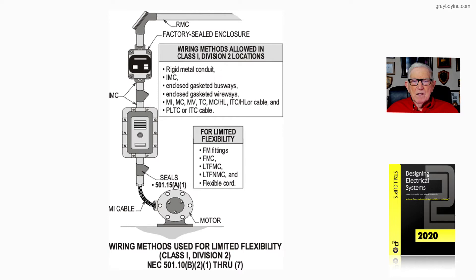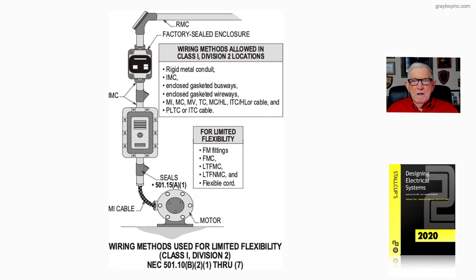Then down at the very bottom, we have a seal and we have MI cable, or we may have a flexible wiring method that is listed for limited flexibility. It's the boxed-in information right next to the motor. We could use FM fittings, FMC fittings, or liquidtight flexible metal conduit or tubing.